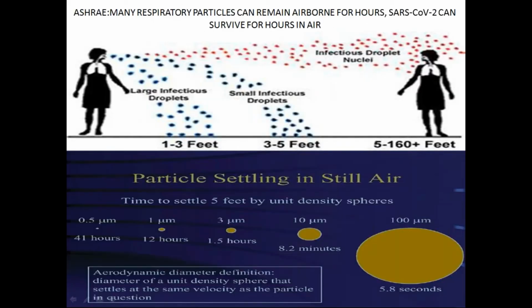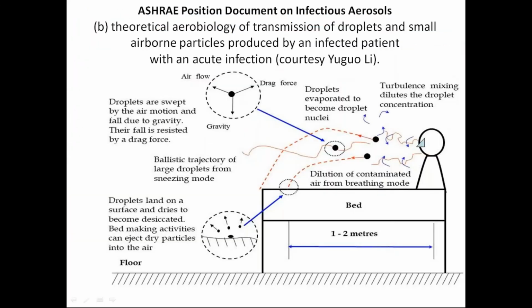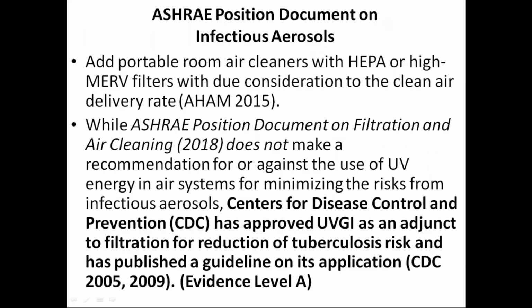ASHRAE gave guidance on particle settling in still air, and we have that as well, and you can read that in your own time. So the CDC has approved UVGI in support of filtration. I'd be thinking that you should have your filtration, or your HEPA filtration, before it, and the UVGI does its work to kill the virus. And they have evidence level A there from that document, which is very good.